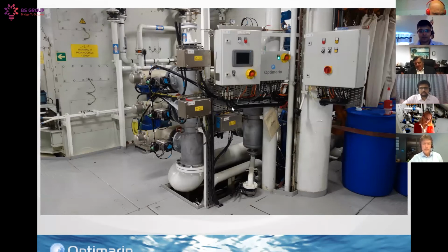One of the added functionalities is automatic flow control. As soon as the UV intensity goes down because of poor water conditions, the flow control will adjust the flow, reducing it so you can still keep going. First, of course, it will increase the power, and if that's still not enough, it will reduce the flow so you stay in compliance. With the new revised G8, that's some new functionality we managed to add.